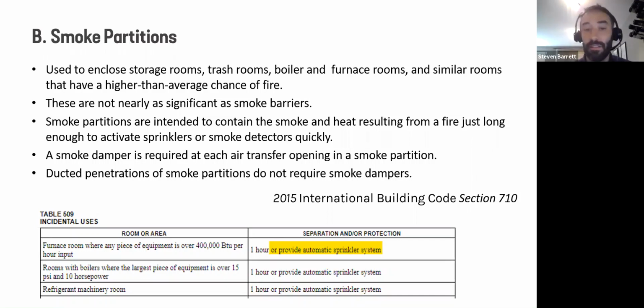Well, most projects have sprinkler systems. So I guess that means we're good, right? We don't have to do anything. Actually, no. And this is something that gets missed quite a bit. If you read that whole chapter 509, it says that if you take the "or provide sprinkler" exception, then that room is a smoke partition. And so what exactly a smoke partition is, it's intended to contain the smoke and heat just long enough to activate sprinklers or smoke detectors quickly. So if you do penetrate it with an air transfer opening, then you do need to provide a smoke damper. But if you're ducted, you do not.